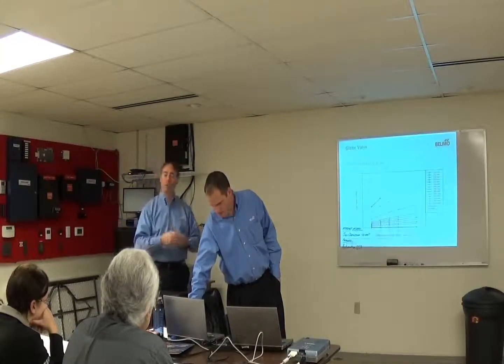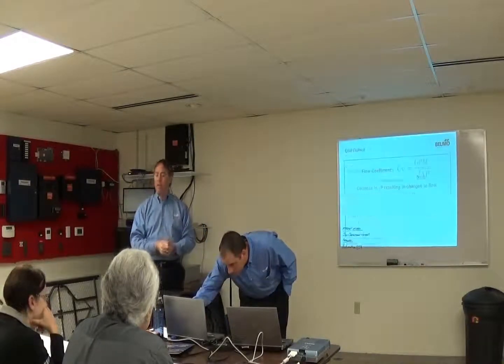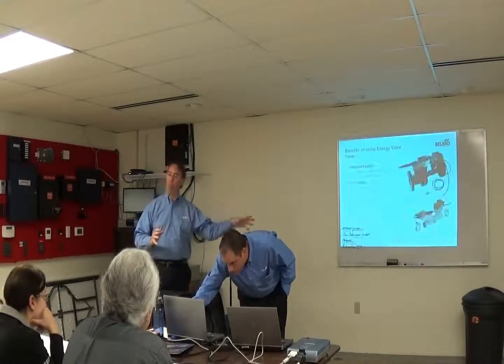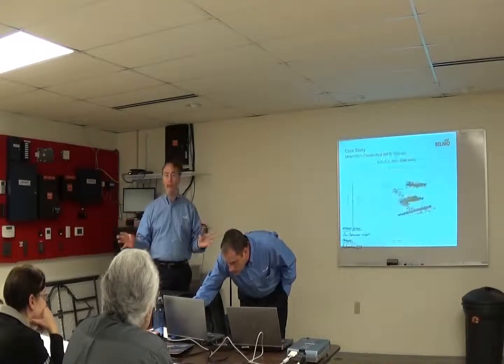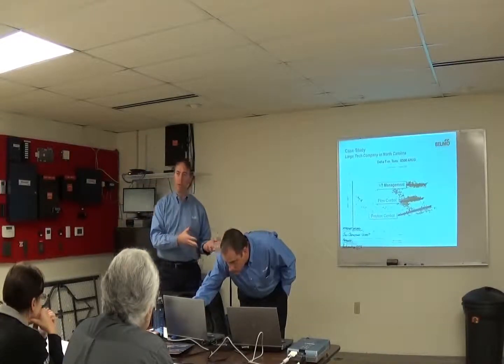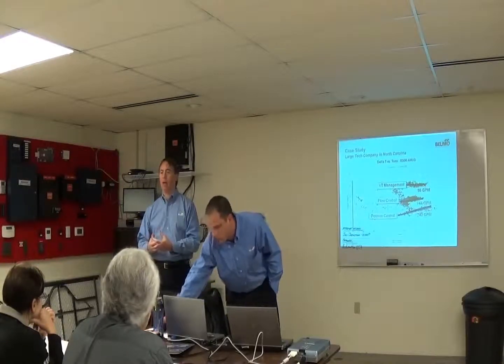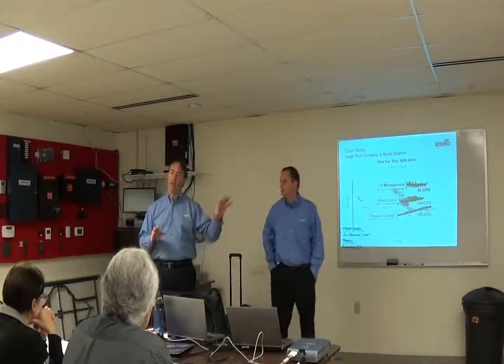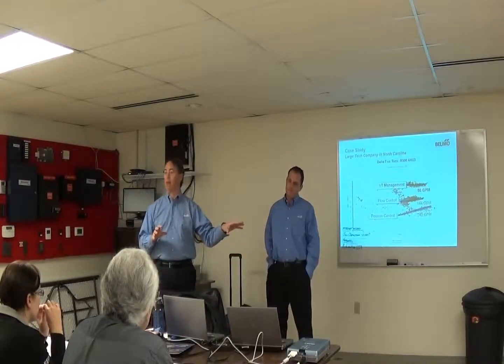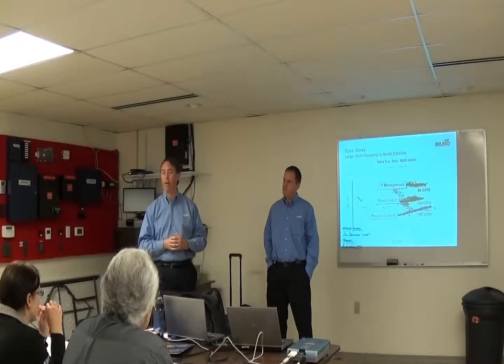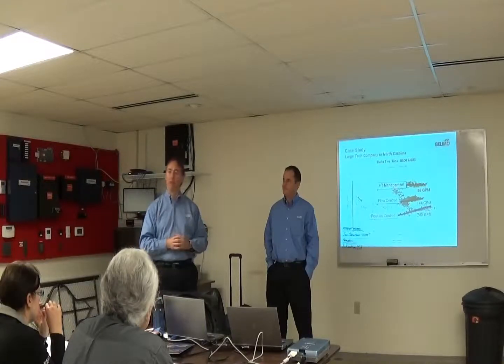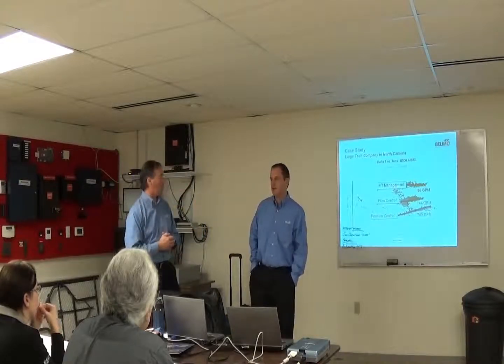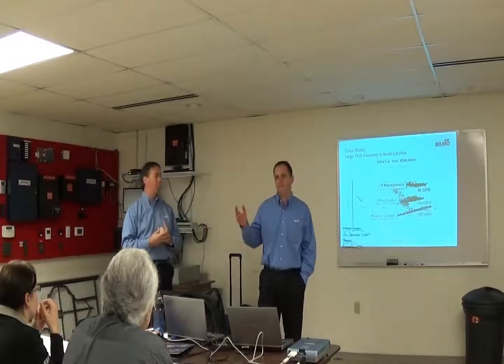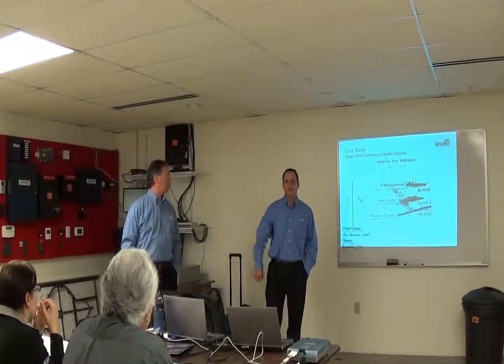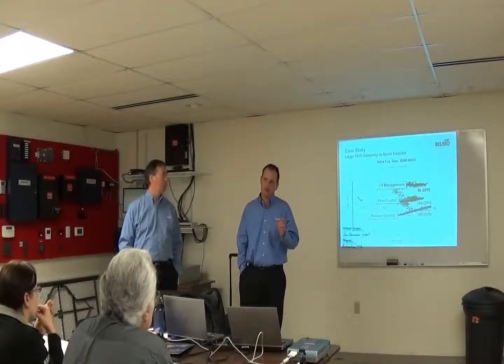But because the guys that are bidding it are so used to bidding pressure dependent, even if it says pressure independent, they still throw in a balancing valve. Even if the spec says otherwise. If there's a pressure independent valve in there, if the engineer is doing it right, they should have eliminated the need for a balancing valve. Now, whoever places the bid may not do that. Yeah, I've told a lot of engineers to put a breakout on your bid form for pressure independent. Start changing the mindset that way, making somebody break it out and show it.